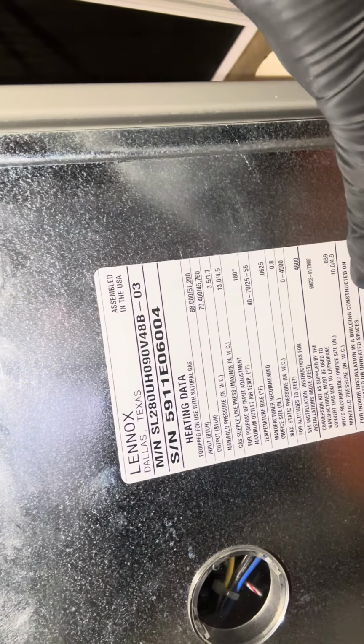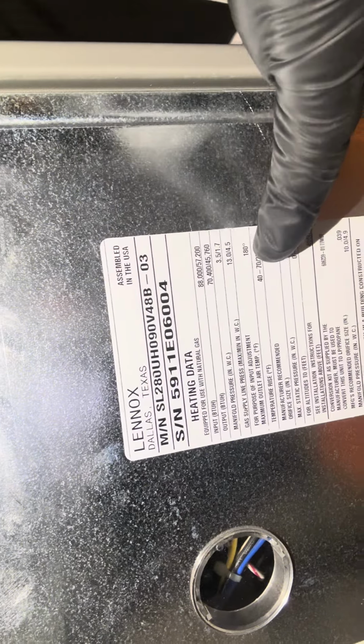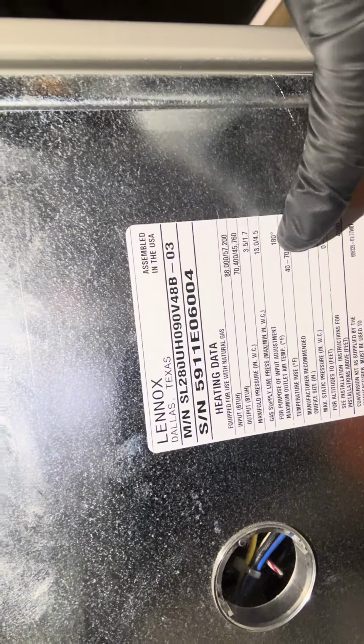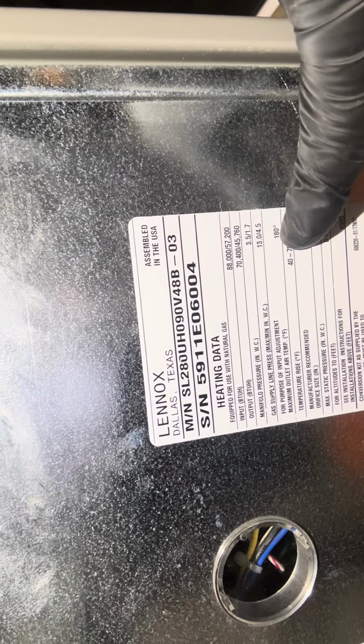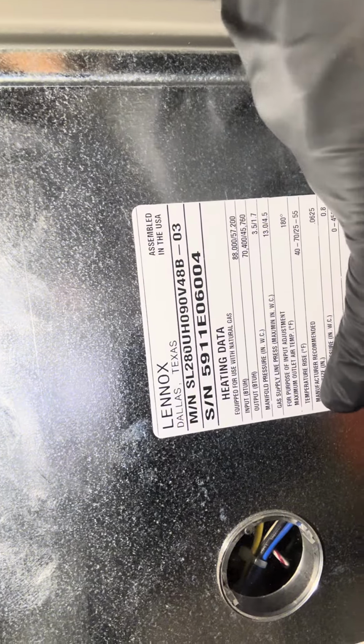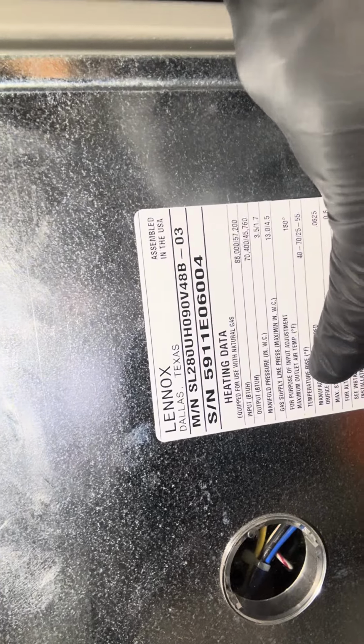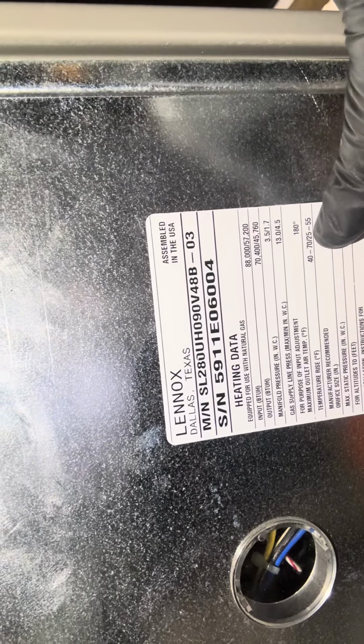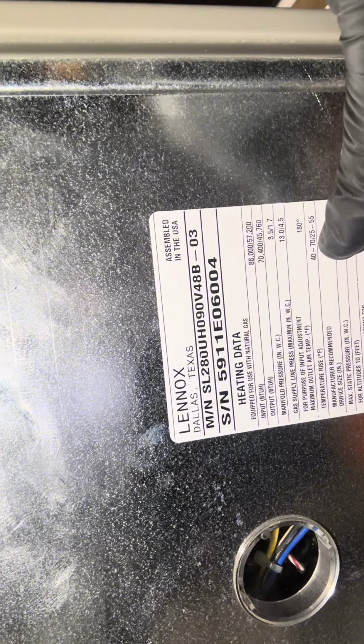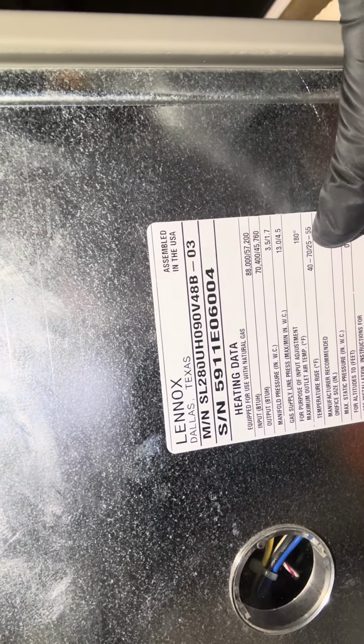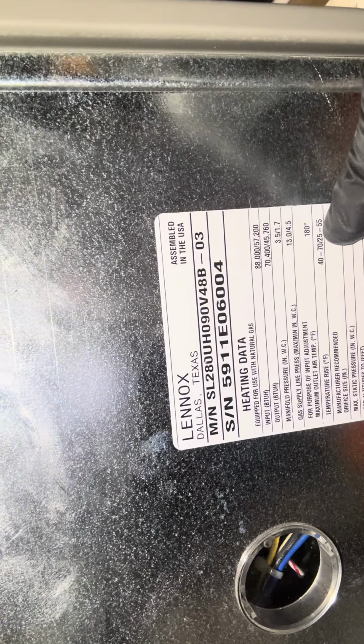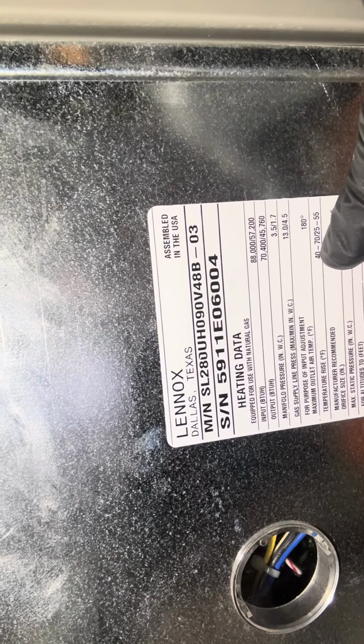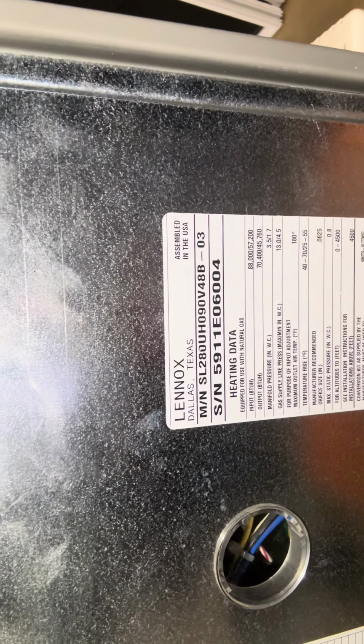While we're here, I also want to show you another thing I'm looking for. This is the maximum outlet air temperature. That is 180 degrees. So if my air gets anywhere near 180 degrees, that is an issue. Another thing we're going to be checking is the temperature rise. This is the manufacturer's guideline on what they want the return air to supply air difference to be. On first stage, the temperature difference should be between 25 and 55 degrees, and on second stage, it should be between 40 and 70 degrees. So as long as I have that, I know I'm good.